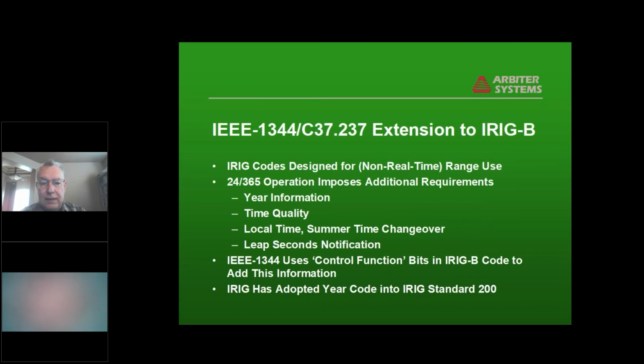We now have extensions to the IRIG code, which are standardized by the IEEE, because the IRIG codes were originally designed for non-real-time applications. So if they knew the time of day, that was good enough. But for operating in the power system, we need more information. We need to know things like what year it is. We need to know what the time quality is. Are we still locked to the source of time, or has the clock drifted out of time because satellite signal is lost or something like that?